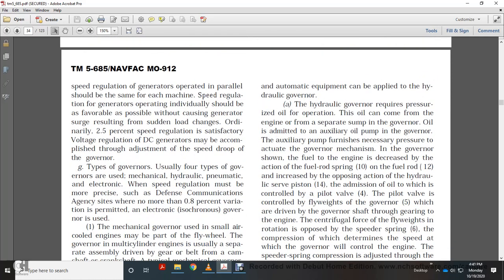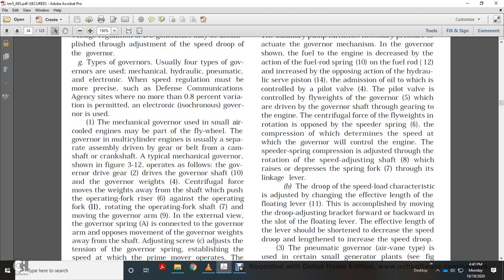There are four types of governors: mechanical, hydraulic, pneumatic, and electronic. Where speed regulation must be more precise — such as in defense communications agencies where no more than 0.8 percent variation is permitted — an electronic isochronous governor is used.